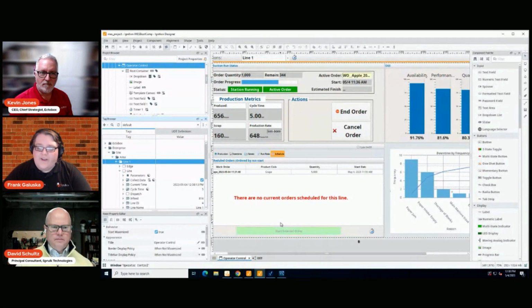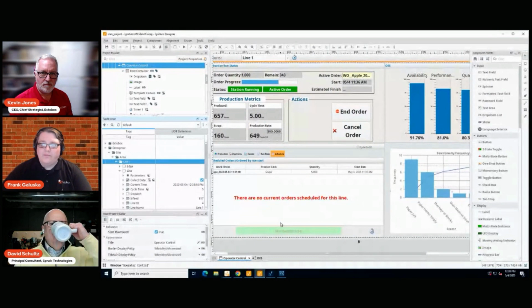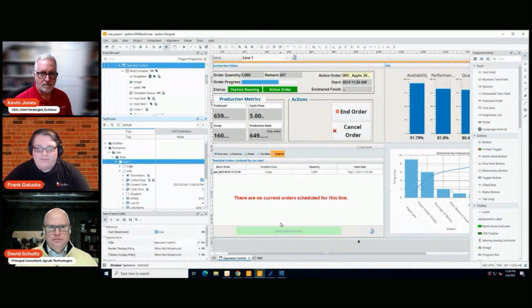Yeah, so I touched on that earlier, but just to reinforce the point, the counter in whatever device, PLC, that we're getting that in-feed and out-feed from might not have the same time parameters that we're looking for, right? It might not care about when shifts start and end. It might not reset in between them, that type of thing. And that's how we're focusing on the data and calculating OEE, on a per run basis. So we don't want to have to worry about that. And like I said earlier, having our run start with an in-feed of anything but 0, we just want to capture the delta so we know exactly what's happening during that run.